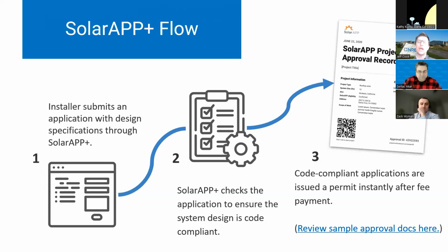That inspection checklist that I mentioned prior is what the inspector would use out in the field, starting at the main panel, working their way up to the roof, if they go on the roof, and if not, performing visual inspections of what's on the roof. Either way, the SolarAPP checklist will tell the inspector what to do at every step of the way. So that's really helpful to a combination inspector if they're not very familiar with solar, or it's just a guide for an inspector that's done 1,000 solar jobs and knows the code like the back of their hand. They can just look at a system and know whether or not it's code compliant. In that case, the SolarAPP checklist is just a guide to help that inspector perform their inspection. And there are sample documents that we can provide if you're interested in seeing them.